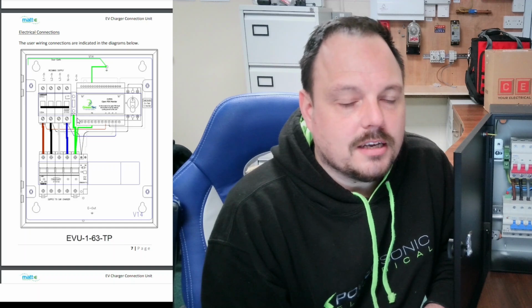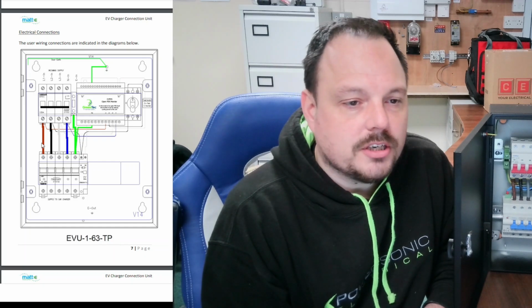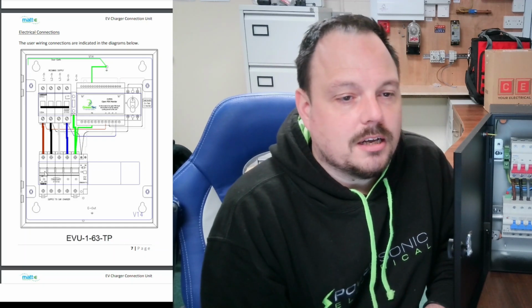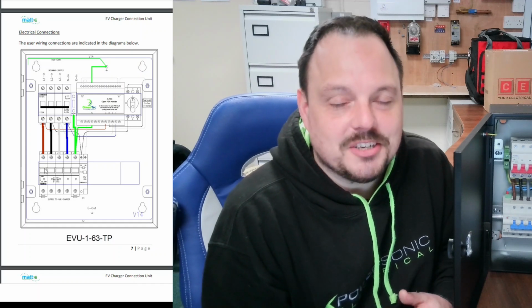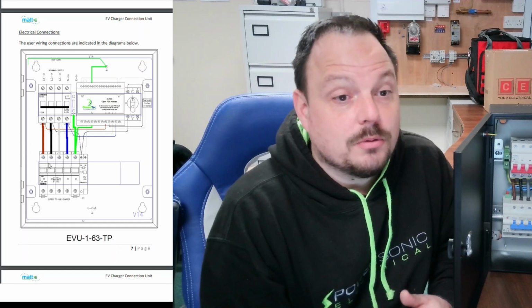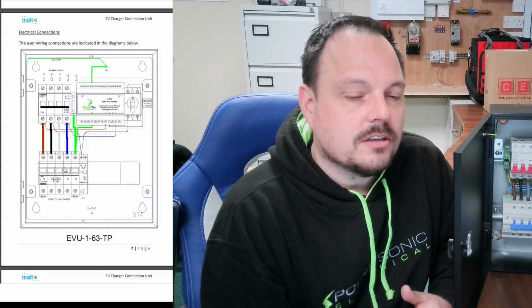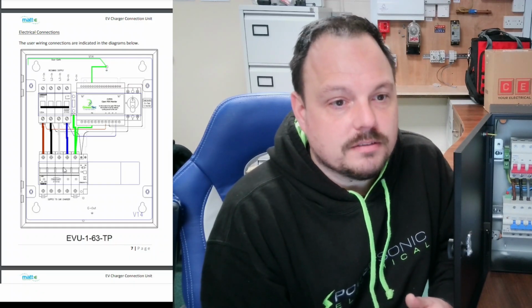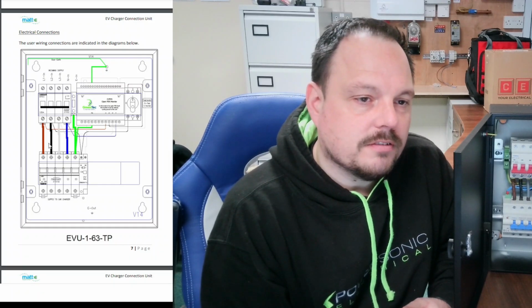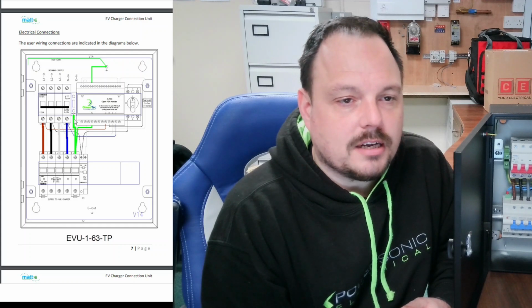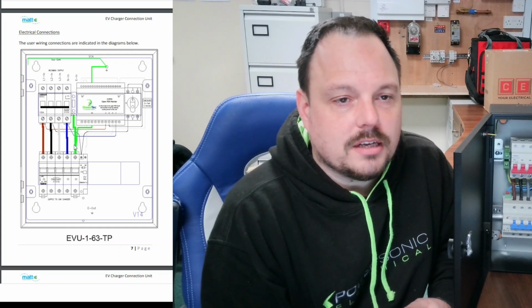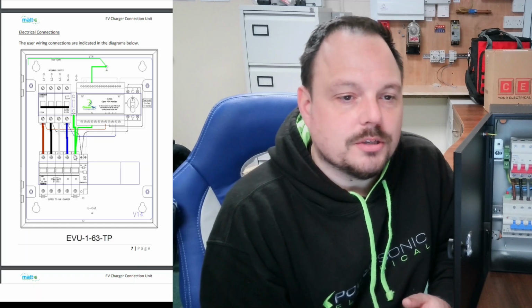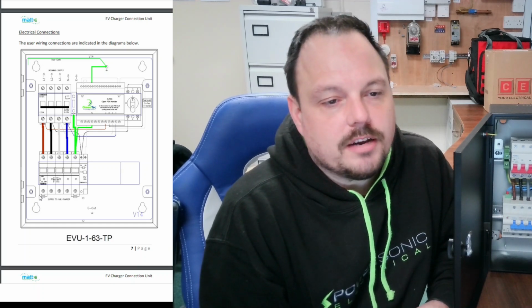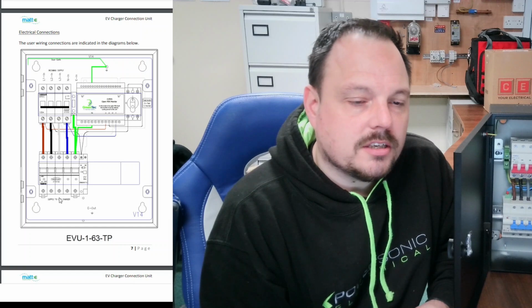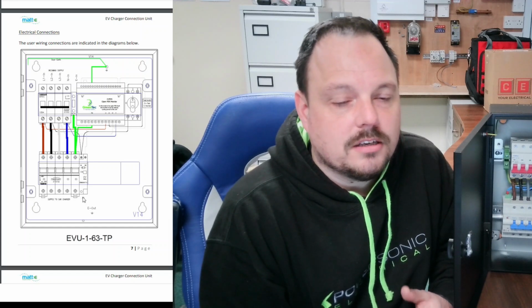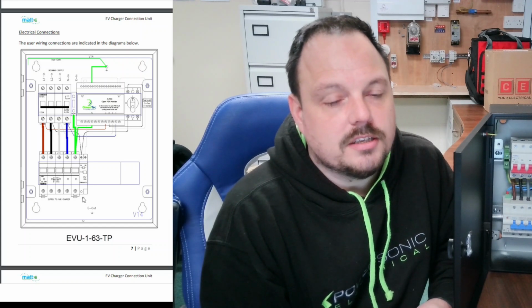And then if you look on the outgoing side of that main switch, it then drops down into this manually resettable switch that will open if any of the phases are lost or there is a rising voltage on the earth. And you can see you've got your L1, L2, L3, neutral and your connection through on that CPC coming into that as well. And then your outgoing circuits to the car charger connect into the bottom of that, and again your CPC needs to be connected into there.